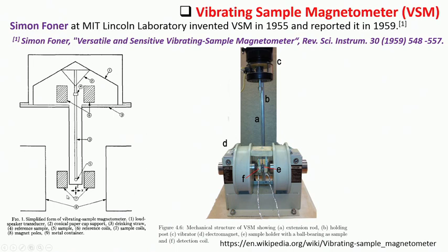Okay. What is there? Here this 8 means the magnet pole. So, these are the magnet. In this experimental setup, we need a magnet. Second, I think here it is 7, these two are coils, sample coils. I will tell the meaning of these sample coils. And here this 5 means the sample, whatever you want to measure. Basically this sample is placed between two pole pieces of a magnet, to apply magnetic field on the sample.